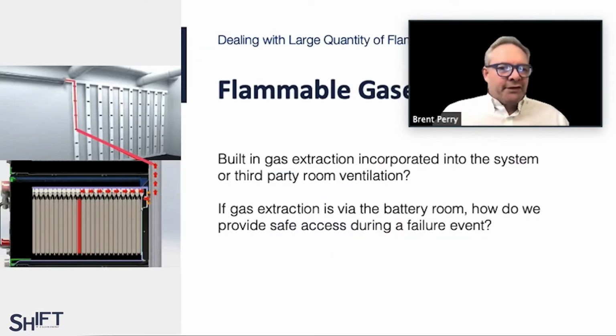And then you have to deal with the gas. So in a lithium fire, the gas extraction and gas management is really where the most critical element occurs. You've already had a failure now. Your cell has failed and is producing gas. Do you expose that gas to the room that the cell is in, which is what happened at the McMicken facility, and then when they opened the door they caused a spark that caused an explosion?